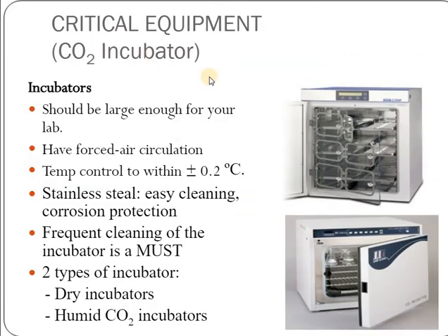Then one of the other critical equipment is the carbon dioxide incubator. These are incubators which should be large enough for the laboratory which has been set up. They have to have forced air circulation. The temperature control should be within plus or minus 0.2 degrees Celsius, that is, it has to be highly sensitive. Stainless steel, easy cleaning, and corrosion protection should be there. Frequent cleaning of the incubator is a must. There are two types of incubator. One is dry incubators, and the other one is humid carbon dioxide incubators.